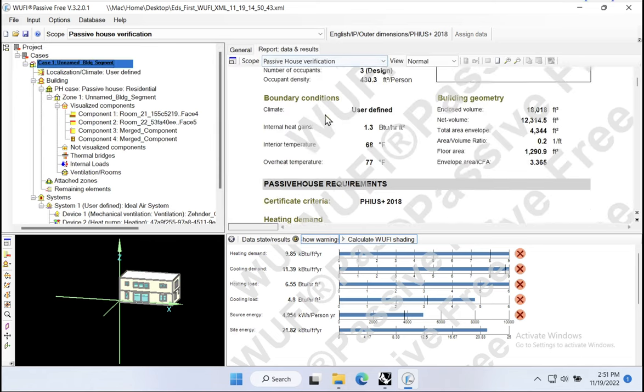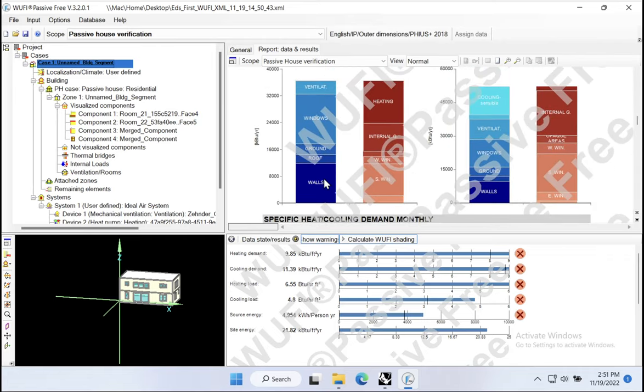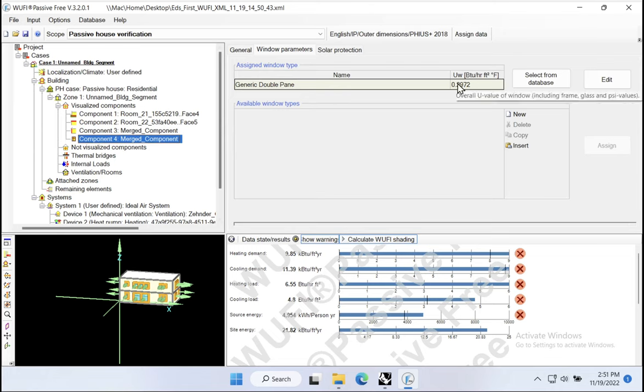Let's go back to our case and come down here. All right. We're already doing really good, right? Our roof has an R50. We have minimized the heat loss there significantly. Better ground contact, better walls. It looks like our walls could still stand to do a little better, but let's see what happens. Clearly, right now, the problem is our windows. Our windows are still terrible. If we take a look at our windows, the out-of-the-box is a code-compliant window, not even in all jurisdictions, but 0.3 for a not very good window. So this is definitely not the type of window that we want to use.